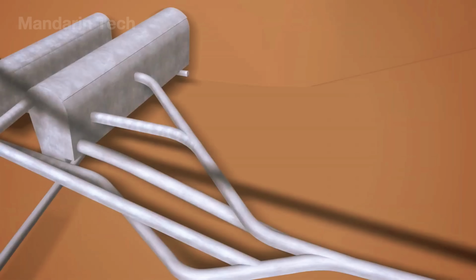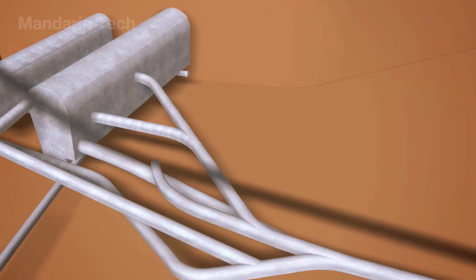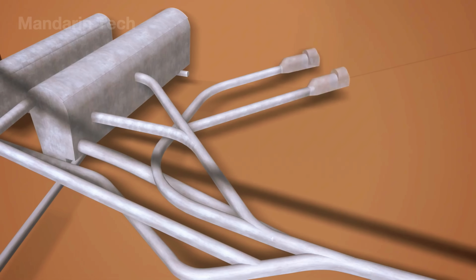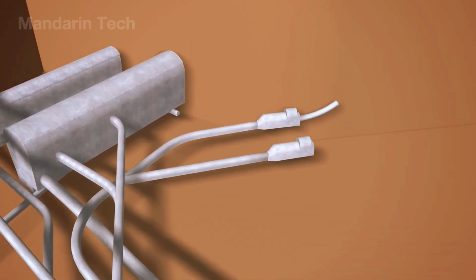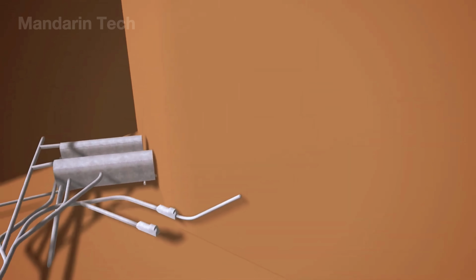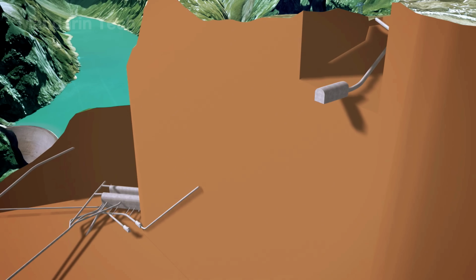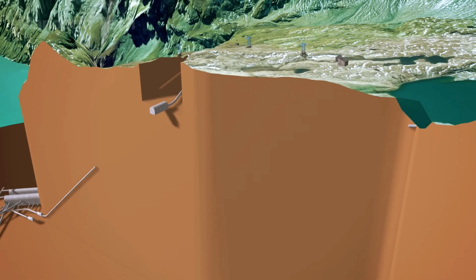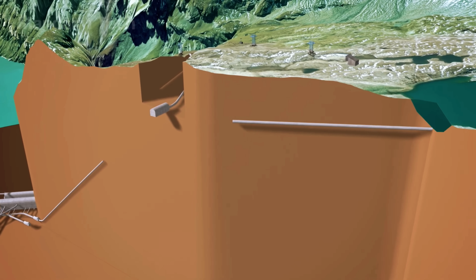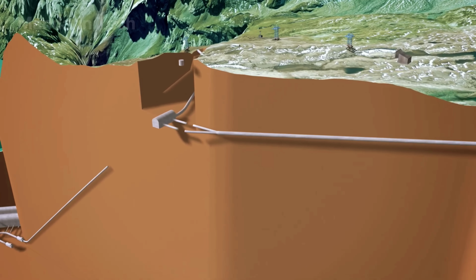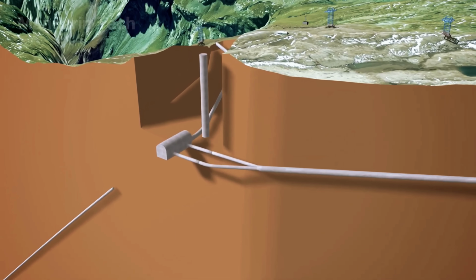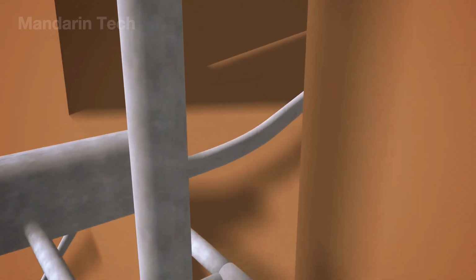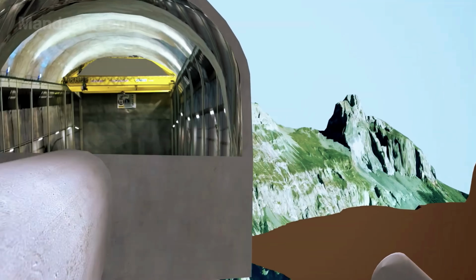At the same time as the powerhouse cavern was being constructed, the pressure shafts carrying water from Lake Mutsi were also built. These shafts were excavated using tunnel boring machines, starting from launch chambers inside the mountain. They descend at an angle of about 40 degrees and end at the valve chamber, located roughly 600 meters lower. In this area, engineers also constructed the upstream pressure tunnel and a surge shaft, a vertical open shaft designed to balance water pressure within the system.